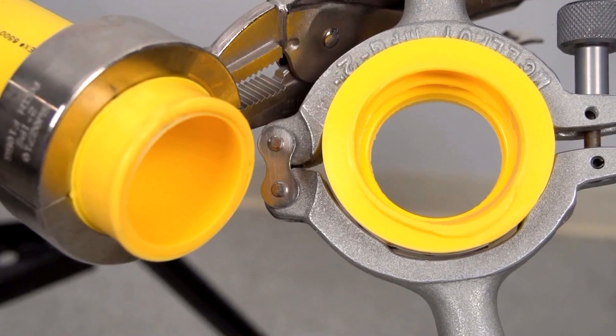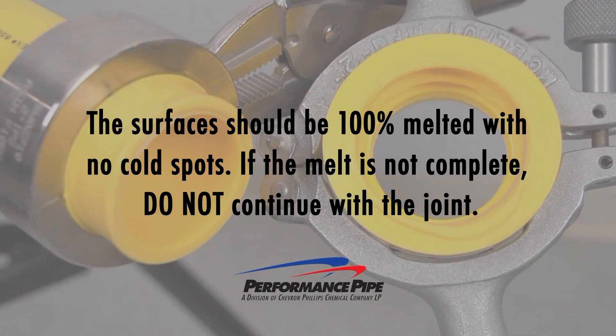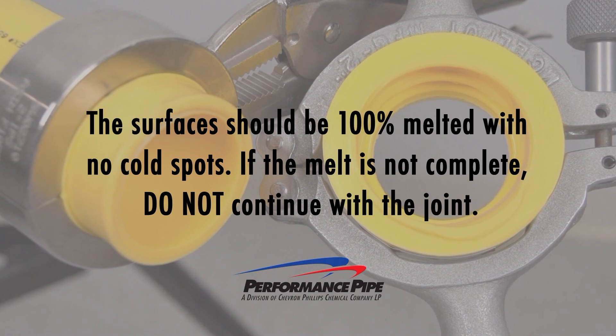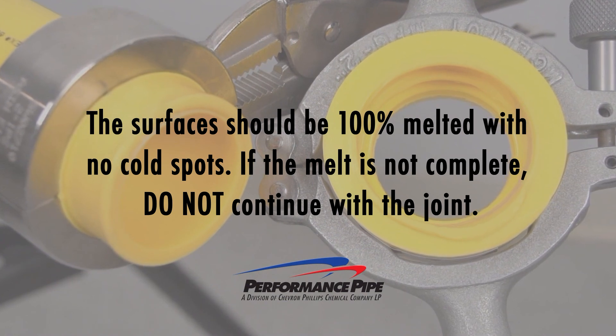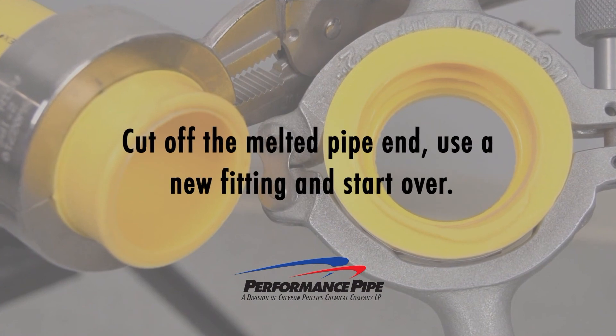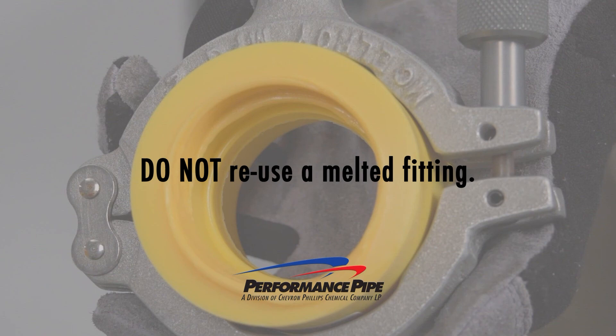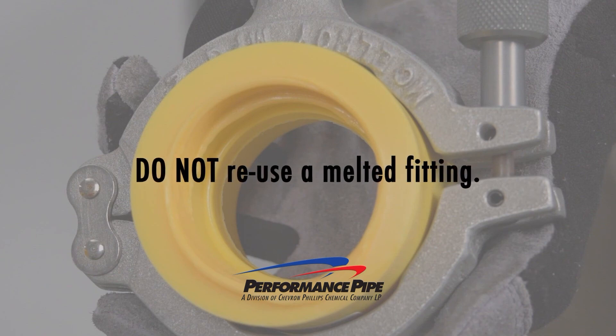Quickly check the melt pattern on the pipe end and the fitting socket. The surfaces should be 100% melted with no cold spots. If the melt is not complete, do not continue with the joint. Cut off the melted pipe end, use a new fitting, and start over from step one. Do not reuse a melted fitting. If the melt is correct, continue the joining procedure.